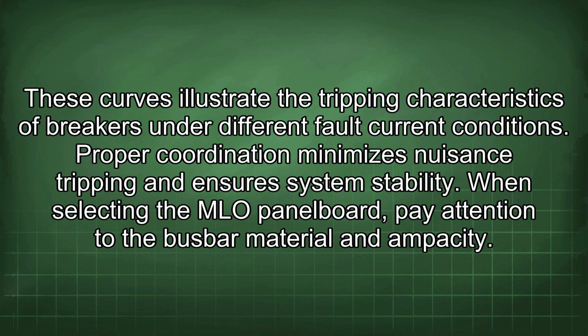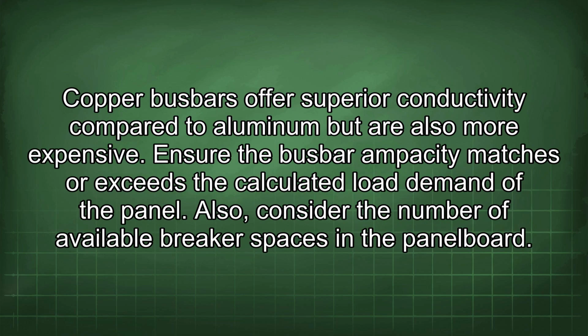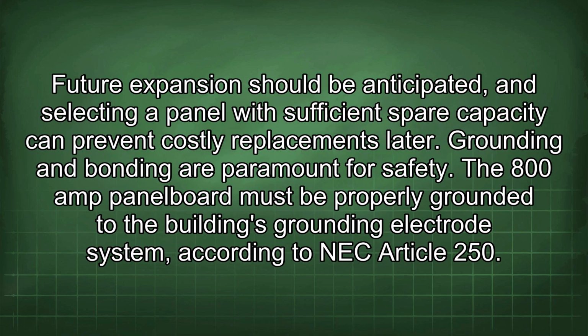When selecting the MLO panel board, pay attention to the busbar material and ampacity. Copper busbars offer superior conductivity compared to aluminum, but are also more expensive. Ensure the busbar ampacity matches or exceeds the calculated load demand of the panel. Also, consider the number of available breaker spaces in the panel board. Future expansion should be anticipated, and selecting a panel with sufficient spare capacity can prevent costly replacements later.